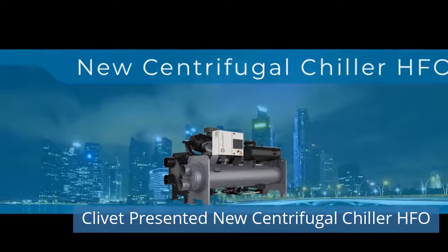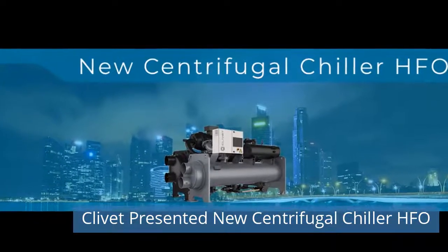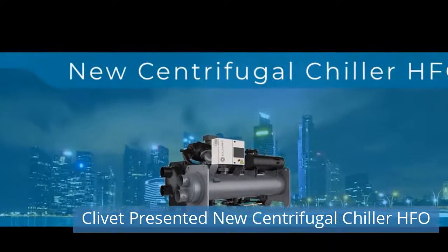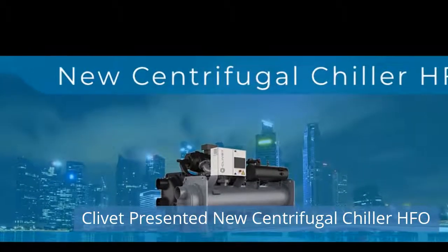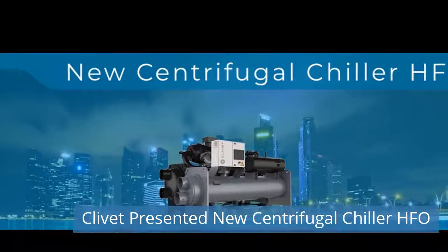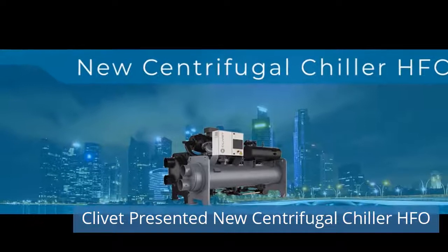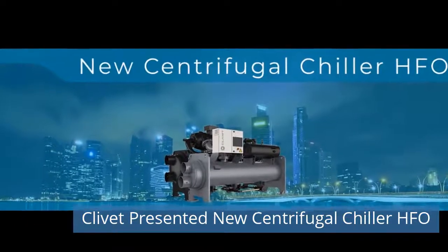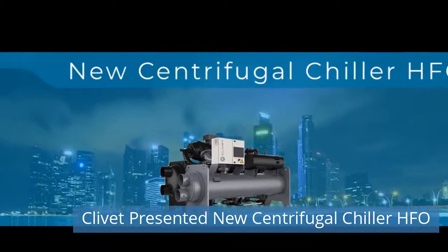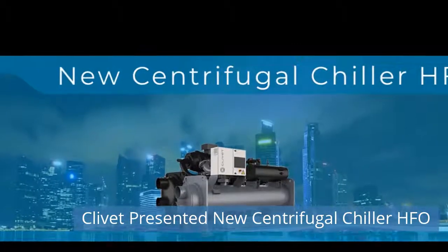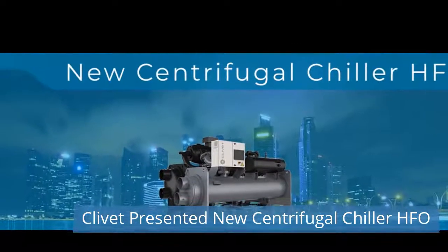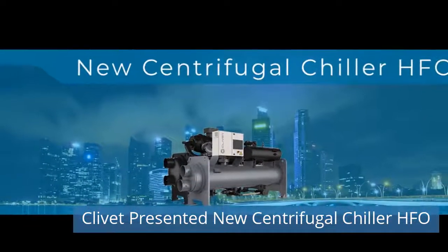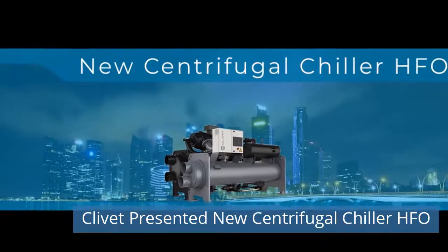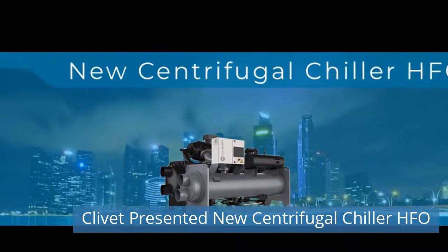WCH series is the new water-cooled liquid chiller for indoor installation, with HFO R1234ZE refrigerant, supplied with horizontal back-to-back centrifugal compressor with inverter regulation. WCH series is available from 810 kilowatts up to 1,600 kilowatts and is the most technologically advanced solution available on the market, able to propose seasonal efficiency values up to 9.64.